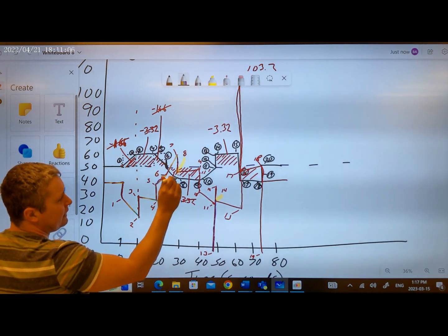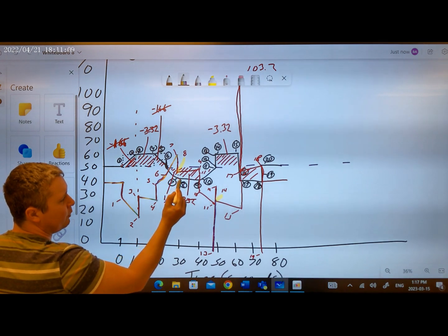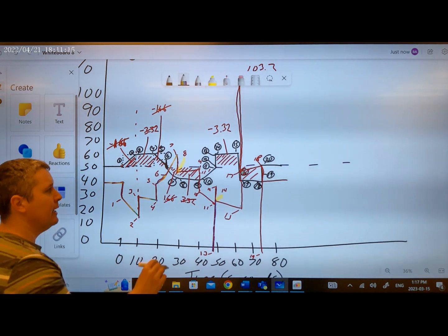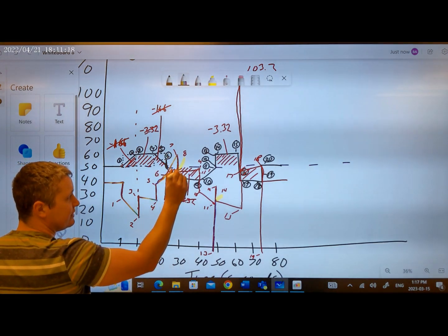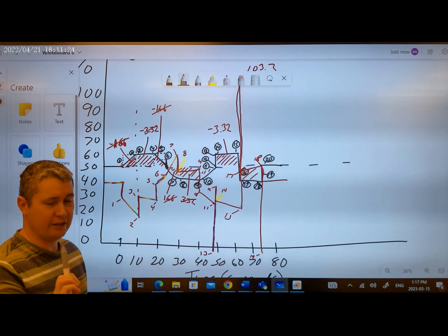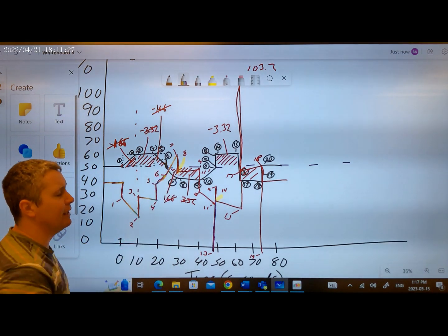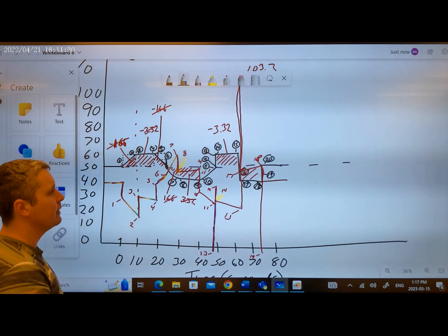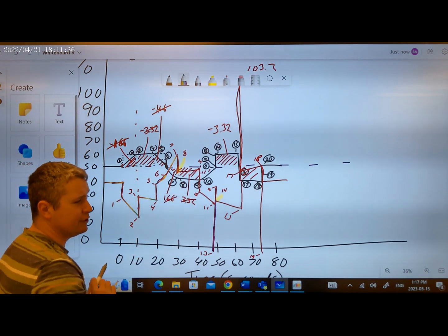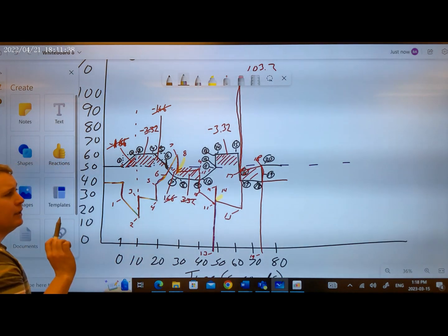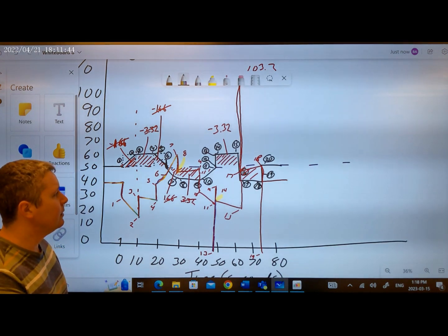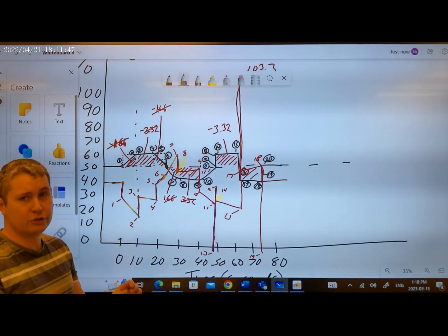And now that we get down to here, by the time we get to 0.8, our derivative stops because our ramp rate stopped. And so our derivative cuts out, and we don't have any more derivative. But that didn't affect our proportional. It didn't affect our integral. The only thing that changed from 0.7 to 0.8 was the derivative. And then as we go from 0.8 to 0.9, our proportional is not changing. Our derivative has no ramp rate, so therefore it hasn't come back. But yet we've gained due to our integral.